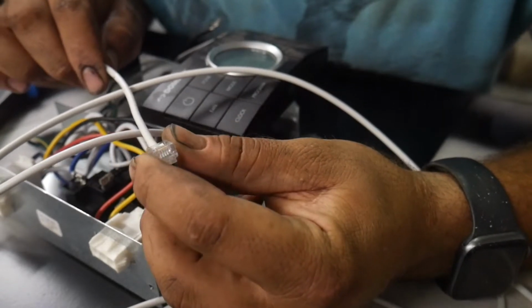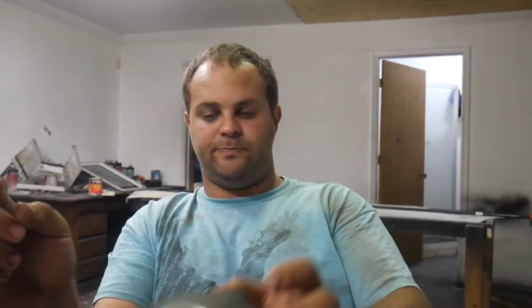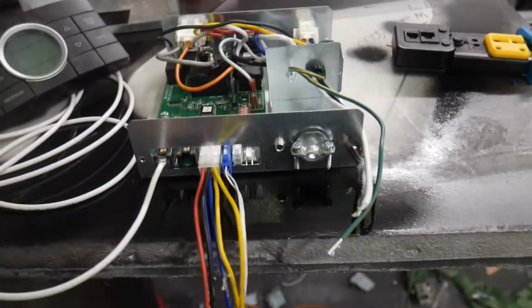I believe it's RJ11. Now, one thing to note, I don't understand why this is, but most of the time when you buy a telephone cable, the polarity is switched on either end because the phone doesn't care about polarity. So the center two conductors will be red and green, and they'll actually be switched on each end of the cable. So even though a phone cord will plug into this, you can't use a phone cord to control this, because this is sending 12 volts DC over this cable to operate the thermostat, and it's got to be polarized correctly. You can't have the positive and negative switched. I was trying to get this to work on the bench here, and I gave up.